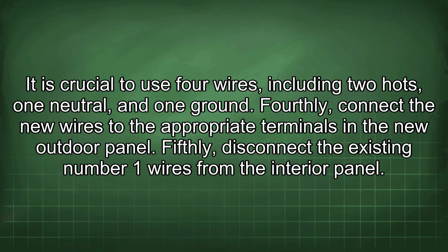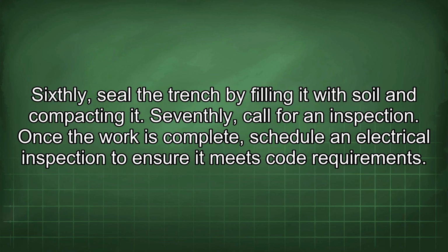Fourthly, connect the new wires to the appropriate terminals in the new outdoor panel. Fifthly, disconnect the existing number 1 wires from the interior panel. Sixthly, seal the trench by filling it with soil and compacting it. Seventhly, call for an inspection. Once the work is complete, schedule an electrical inspection to ensure it meets code requirements.